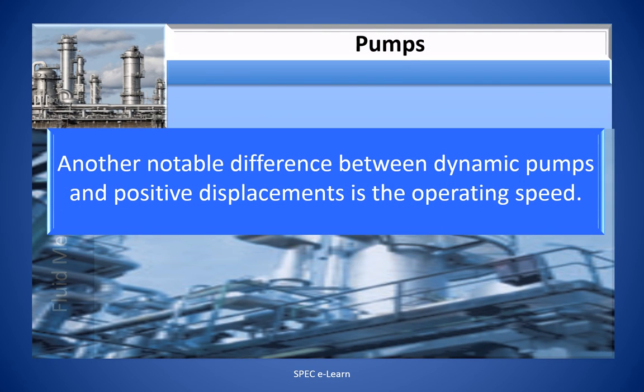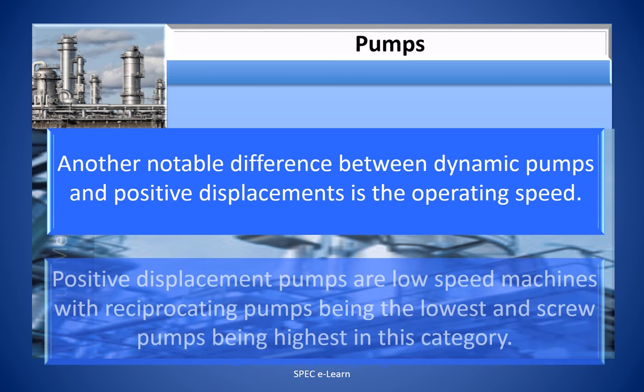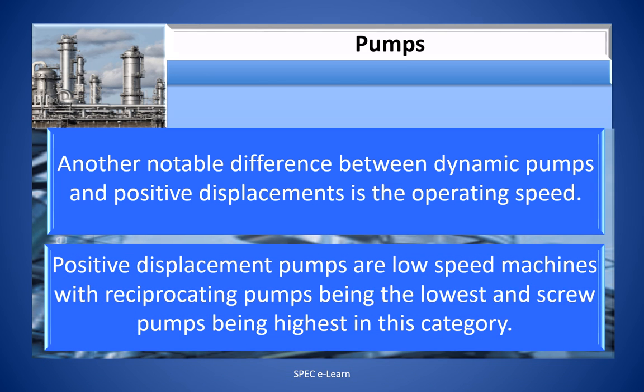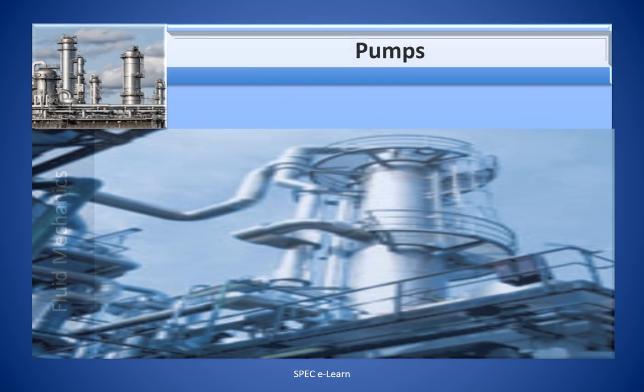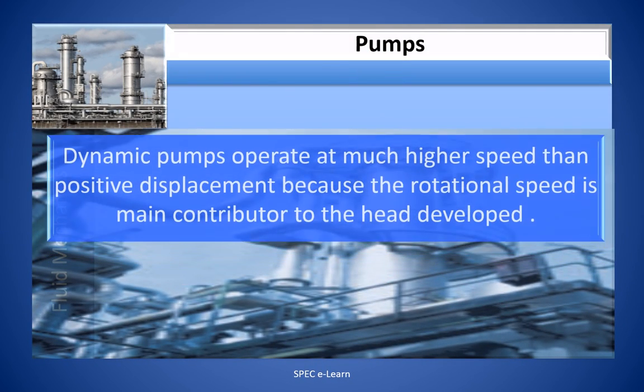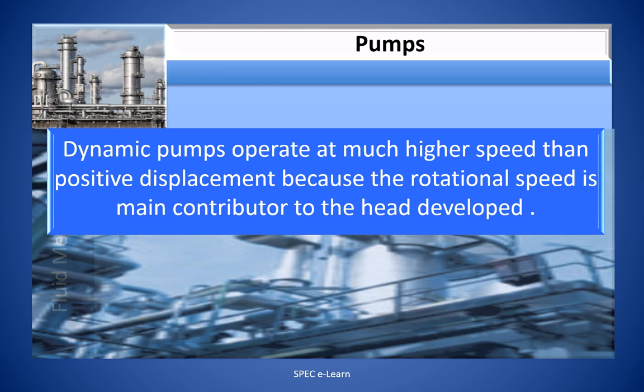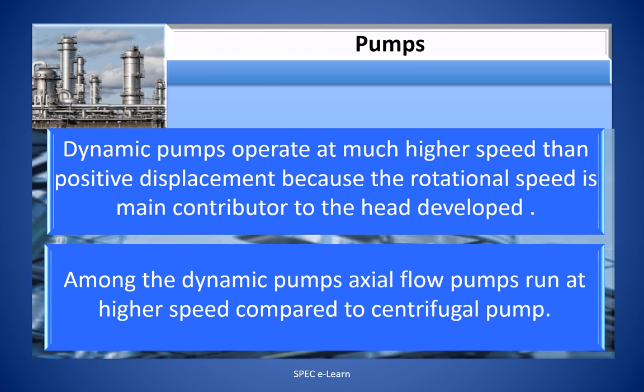Another notable difference between dynamic pumps and positive displacement pumps is operating speed. Positive displacement pumps are low-speed machines, with reciprocating pumps being the lowest and screw pumps being the highest in this category. Dynamic pumps operate at much higher speed than positive displacement pumps because the rotating speed is a main contributor to the head developed. Among dynamic pumps, axial flow pumps run at higher speed compared to centrifugal pumps.